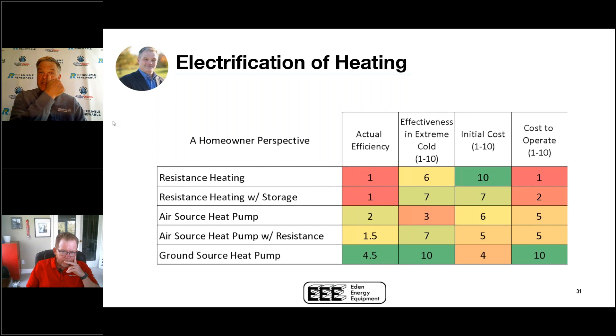You may look, for instance, at the air source heat pump with a COP of 3.5 in an advertisement or brochure. Please understand that's for 47 degrees Fahrenheit, or about 8 degrees centigrade. That's the temperature at which air source heat pumps are measured and advertised, that's the number. So if you're looking at outdoor air temperature, that's important - the COP you see advertised, and it happens frequently, that's at 8 degrees.